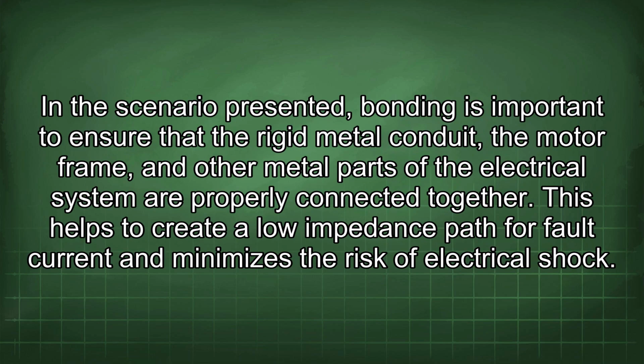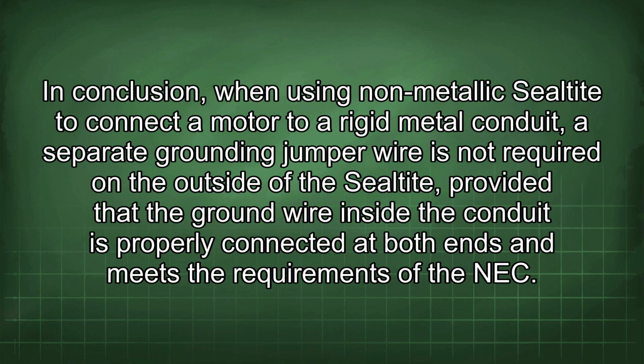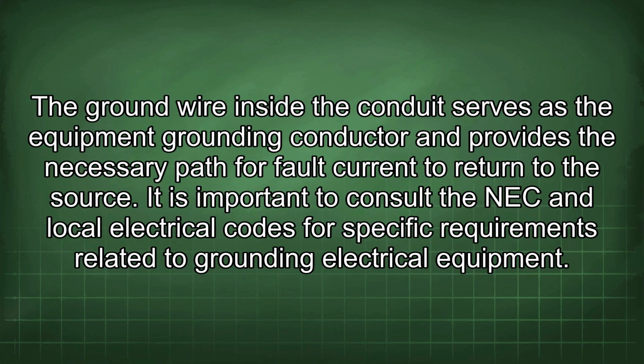In the scenario presented, bonding is important to ensure that the rigid metal conduit, the motor frame, and other metal parts of the electrical system are properly connected together. This helps to create a low impedance path for fault current and minimizes the risk of electrical shock. In conclusion, when using non-metallic Sealtite to connect a motor to a rigid metal conduit, a separate grounding jumper wire is not required on the outside of the Sealtite, provided that the ground wire inside the conduit is properly connected at both ends and meets the requirements of the NEC. The ground wire inside the conduit serves as the equipment grounding conductor and provides the necessary path for fault current to return to the source.